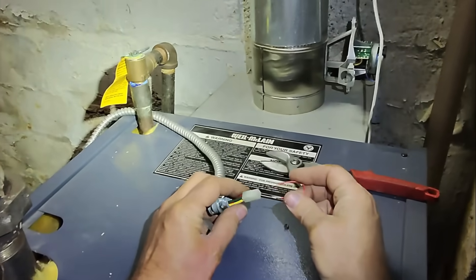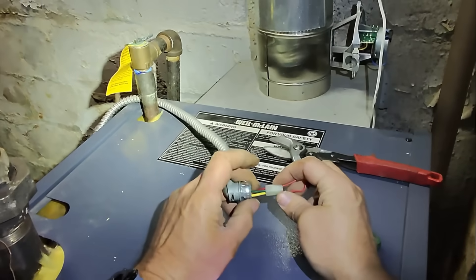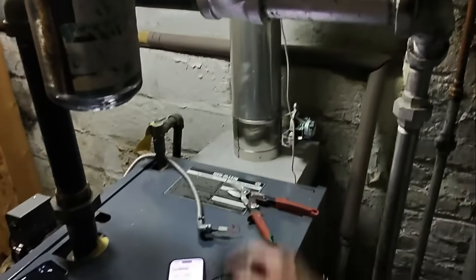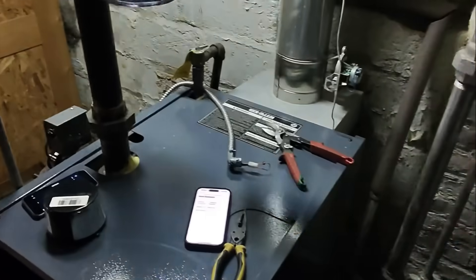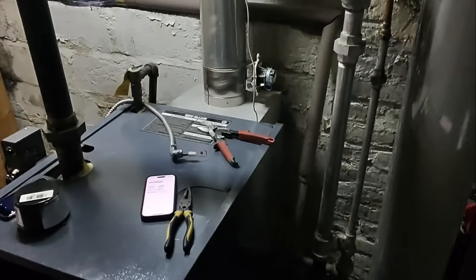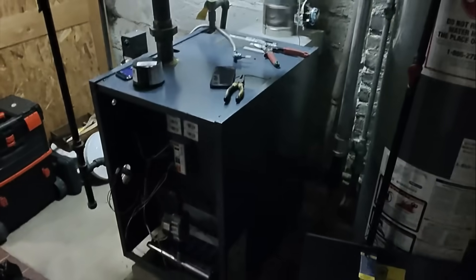All right — that's the red and the yellow. There's red, and there's yellow. And now the burner is running. We've mechanically and electrically removed the damper. We're going to turn the boiler off, take the guts out, and permanently make that jumper so we can replace her vent damper next week while she continues to wake up every morning to a nice, warm, toasty home.